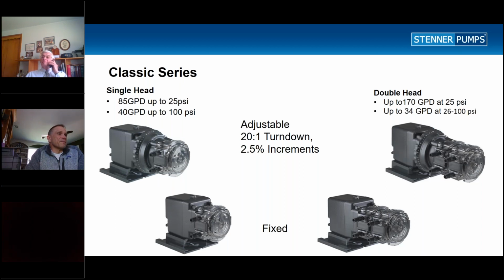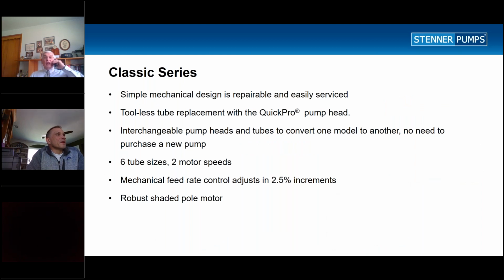Fixed pumps would typically be used in cases where you're connecting the pump to a pump control module, which is then connected to a water meter. So in some home applications, if you want to try to eliminate going to the feed rate control, you can do that with a fixed pump by connecting it to a pump control module. The classic is just easy. It's an easy, simple design, easy to maintain with the different tube sizes.